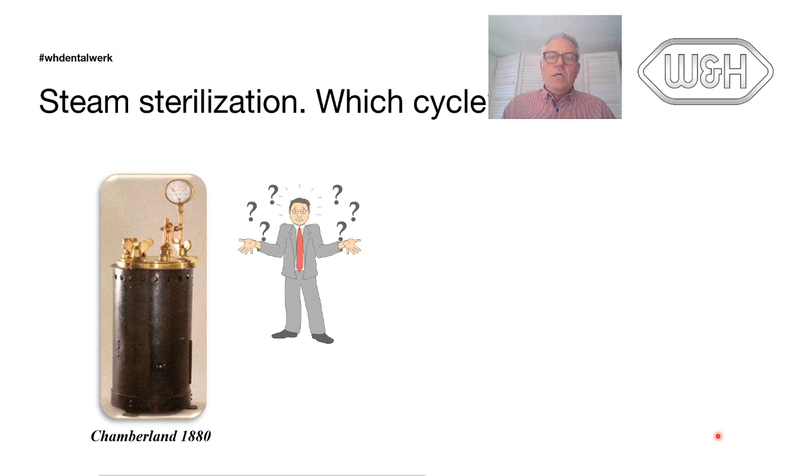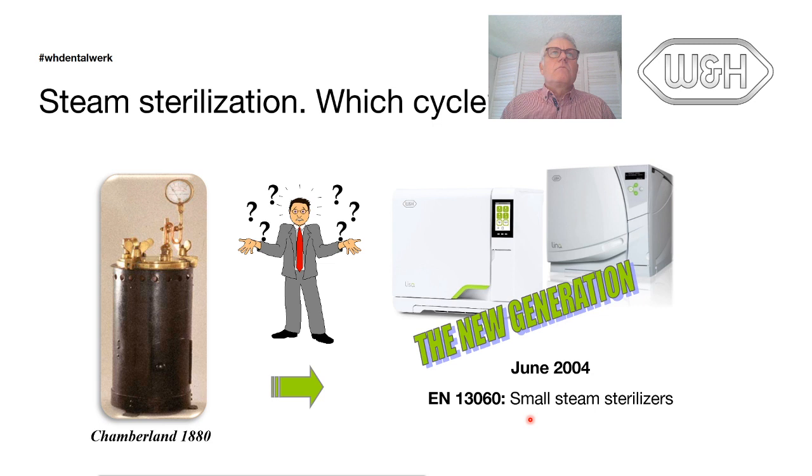Now, as you could see, the main result is 121, 15 minutes. I just want to point out, I'm French, and I know in my country there is no official release for this technique. So I know there are French dentists listening to me. I'm sorry, but in France, so far, I have not heard about any guideline or acceptance of this technique. Now, we talk about steam sterilization.